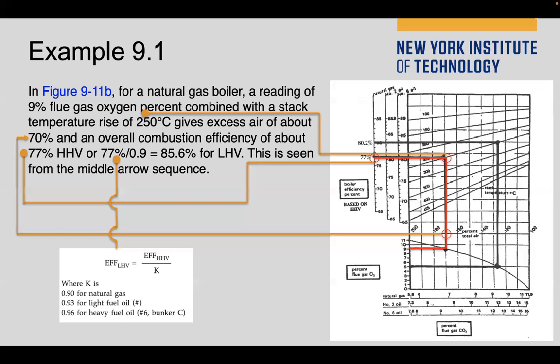Just so you know, if you want the boiler efficiency to increase, a higher stack temperature is not the favorable one. I mean, if we can have a lower temperature, that means more energy is applied in a useful way rather than wasted. But if the stack temperature is high, that means much energy will go to the stack and heat up the atmosphere, raising the temperature.